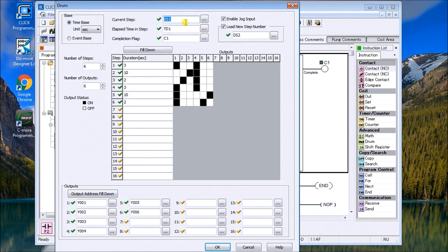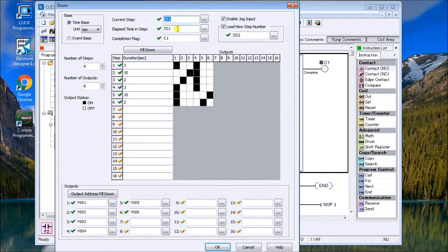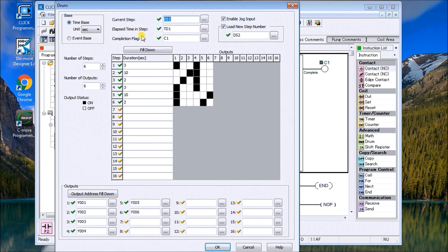Elapsed time in steps is a timer value, so we use TD1, and a completion flag. This is what happens when you reach the end of your drum sequence. Then we have an enabled jog input, so the enabled jog input, what it will do is when you activate this, it'll actually add another input to your drum sequence so that you can jog it.